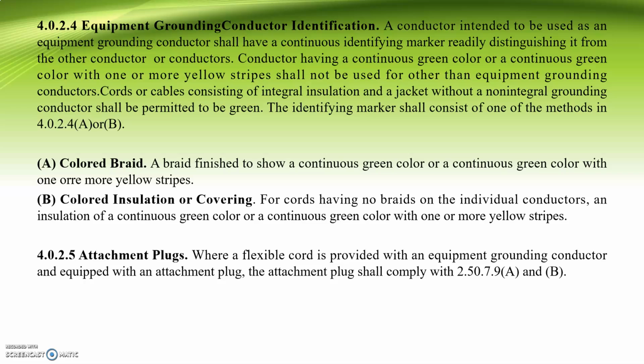So A, colored braid. A braid finish to show a continuous green color or a continuous green color with one or more yellow stripes. So B, colored insulation or covering. So for cords having no braids on the individual conductors, an insulation of a continuous green color or continuous green color with one or more yellow stripes. So chapter 4.0.2.5, so attachment plugs. So if a flexible cord is provided with an equipment grounding conductor and equipped with an attachment plug, the attachment plug shall comply with chapter 2.50.7.9 A and B.